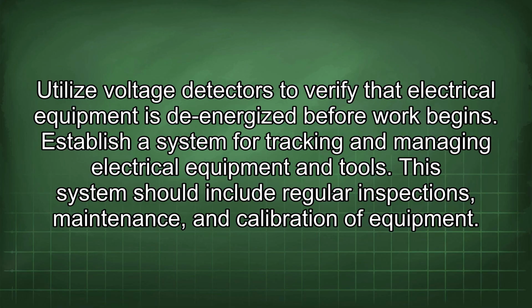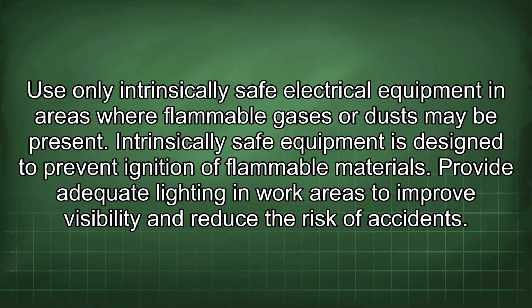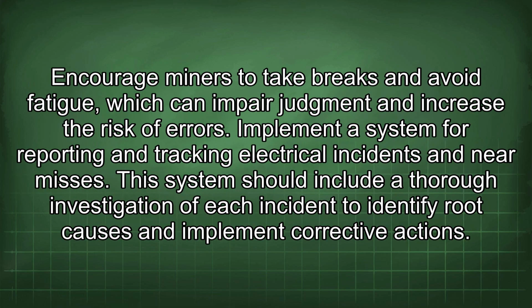Establish a system for tracking and managing electrical equipment and tools. This system should include regular inspections, maintenance, and calibration of equipment. Use only intrinsically safe electrical equipment in areas where flammable gases or dust may be present. Intrinsically safe equipment is designed to prevent ignition of flammable materials. Provide adequate lighting in work areas to improve visibility and reduce the risk of accidents. Encourage miners to take breaks and avoid fatigue, which can impair judgment and increase the risk of errors.